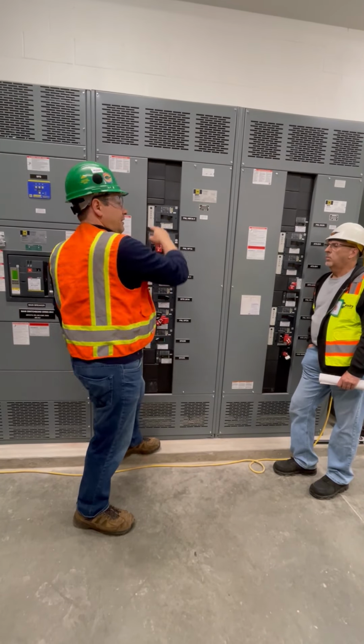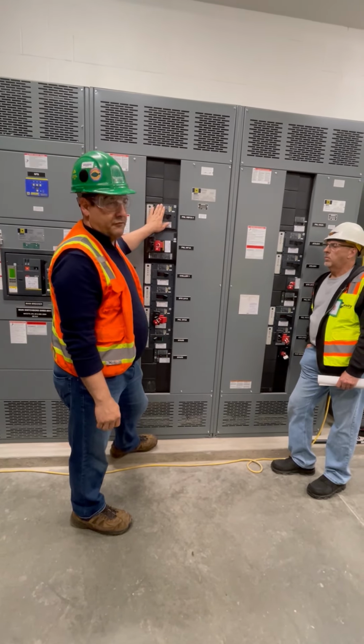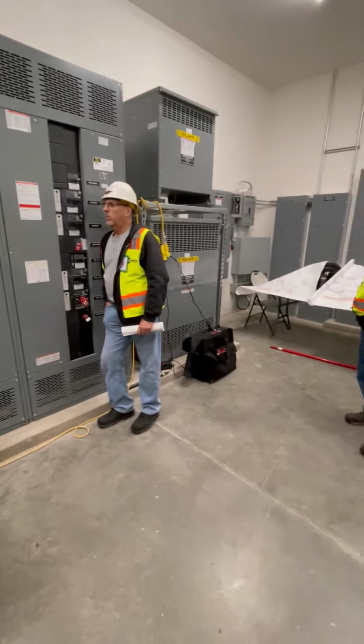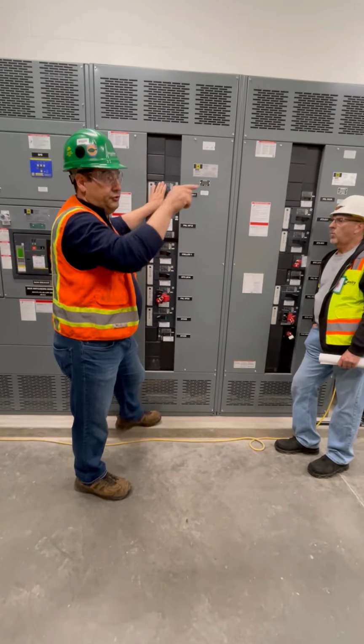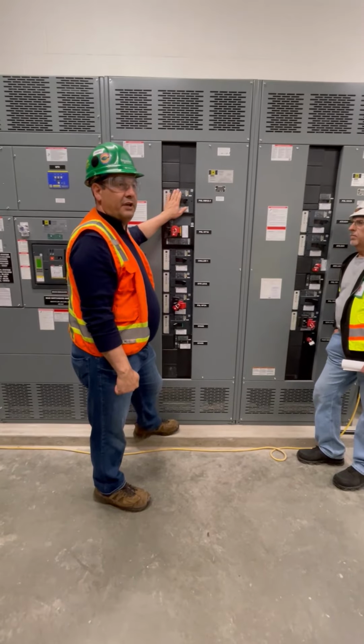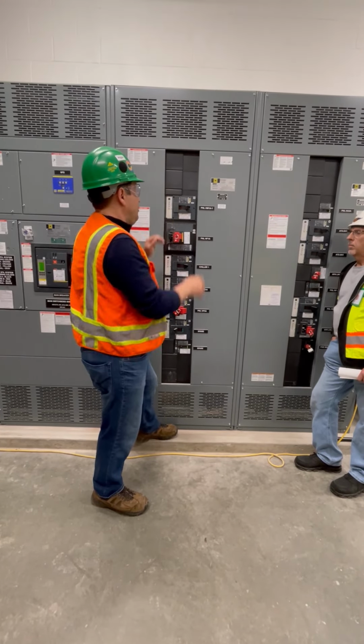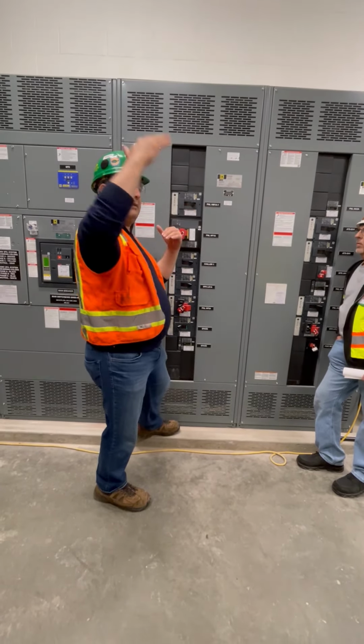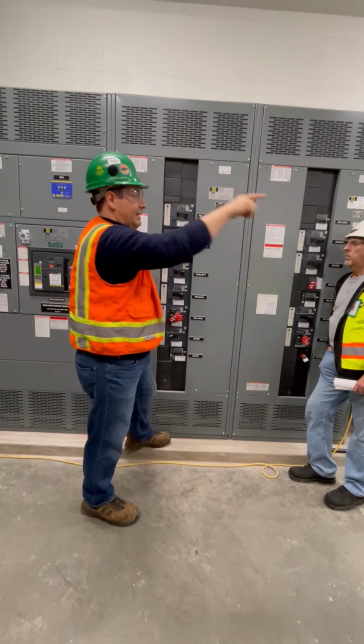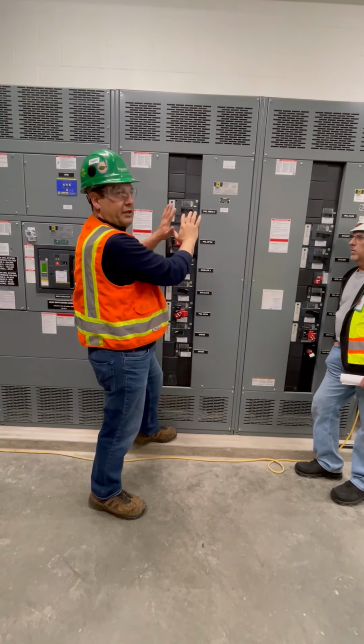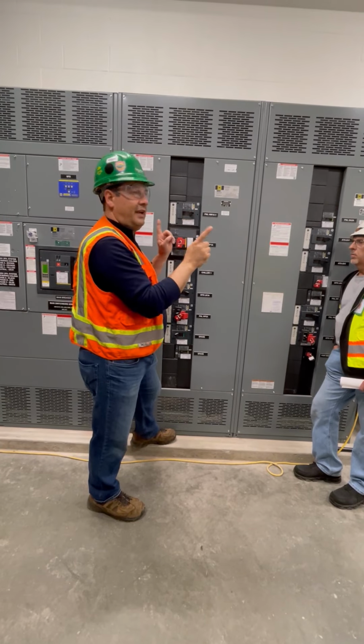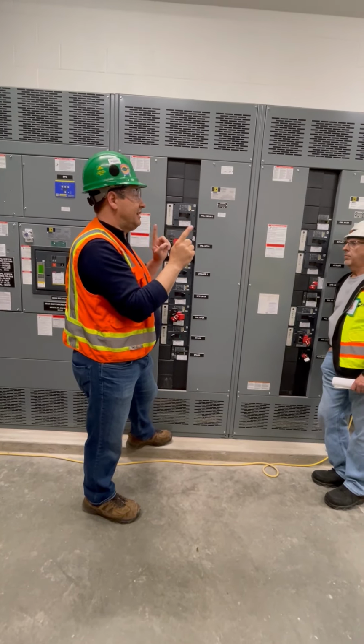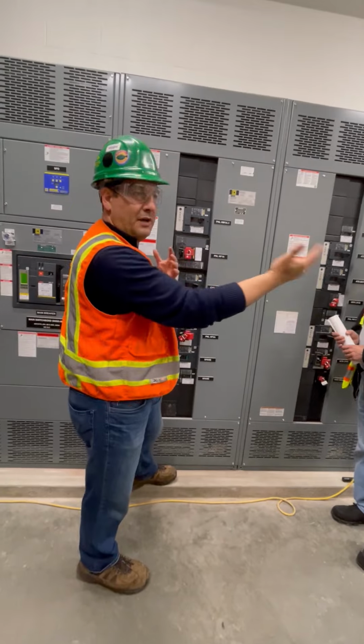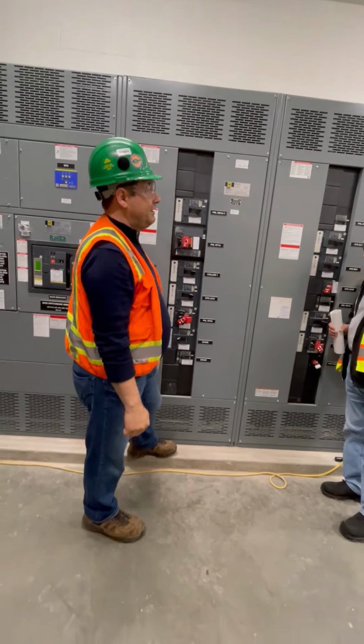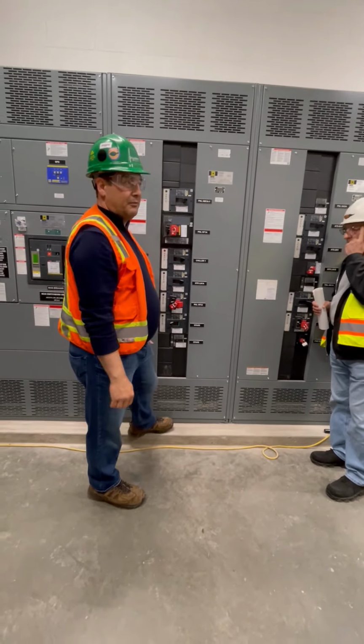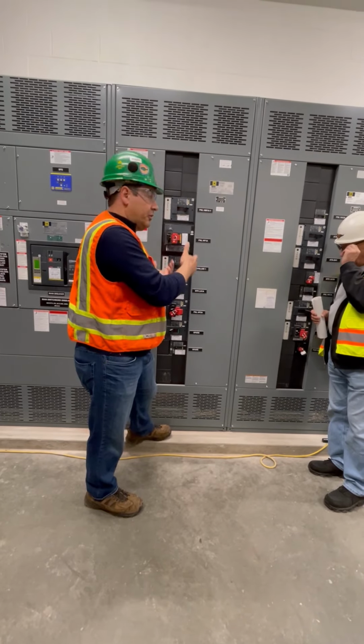you take it from there and plug it in here, you may create an issue for yourself because those breakers are probably rated at a lower level. Those could be at 35 kA at 480. These are 65 kA at 480. You can take this one and plug it in there because it'll be way above its withstanding rating, but you cannot take a breaker from there. Although it's the same breaker, the only difference is that kA rating of the breaker itself. So something to keep in mind if you're ever swapping breakers while you're operating a switchboard is making sure that you plug the right breaker in the right switchboard so you don't create issues.